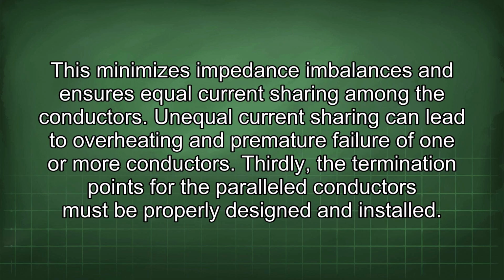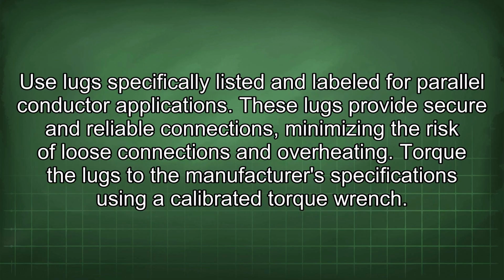This minimizes impedance imbalances and ensures equal current sharing among the conductors. Unequal current sharing can lead to overheating and premature failure of one or more conductors. Thirdly, the termination points for the parallel conductors must be properly designed and installed. Use lugs specifically listed and labeled for parallel conductor applications. These lugs provide secure and reliable connections, minimizing the risk of loose connections and overheating. Torque the lugs to the manufacturer's specifications using a calibrated torque wrench.